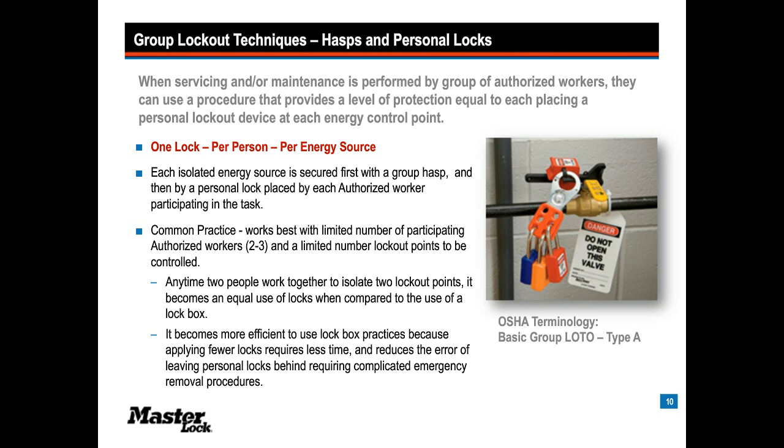Now, a common practice that I've seen in many places and like quite a bit is the idea that anytime a person locks out a device, whether it be an electrical disconnect or a valve or whatever may be being secured, they start with a hasp, and right off the bat, that provides the space for others to join them if necessary. If it's only them, the hasp was there, it secured the device, the lock was in place, but if somebody has to join, there is no unlocking and relocking. There's only the addition of the new person's lock to the hasp.